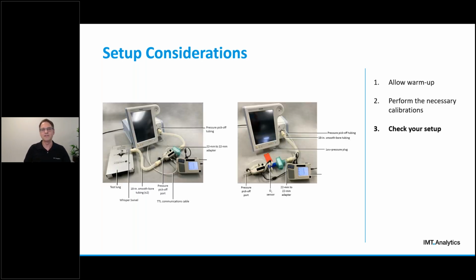Here are 2 measurement setup pictures from a service manual of a ventilator manufacturer. The pictures are actually pretty good, even though, for example, this teed-in pressure here is quite hard to see. The issue here is that this quite complex setup is based on the specific gas flow analyzer they selected for this picture. As you can see, it consists of multiple parts. We have a flow module, we have a measurement module, and we have an O2 sensor module as well. We have a trigger cable that goes to the ventilator in this picture here. And this is all based on that specific device. So what if you want to use a different analyzer? In such cases, this manufacturer just leaves it to you to figure out how your setup has to look.